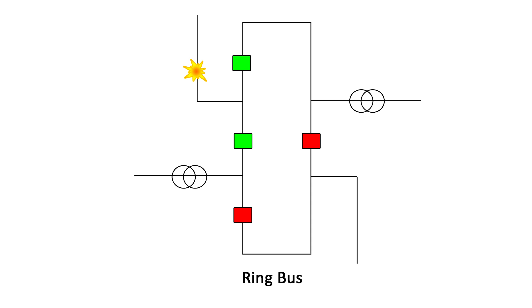The main disadvantage of the ring bus system is that if a fault were to occur, the ring is split, which could result in two isolated sections. Each of these two sections may not have the proper combination of source and load circuits. This can be somewhat avoided by connecting the source and load circuits side by side.